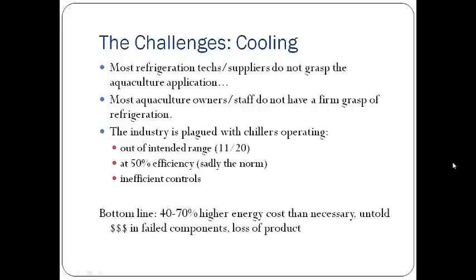In fact, they didn't even publish any data for the range that they were being operated in. So they were being run very inefficiently. But even some of the ones that were in the intended range were operating at roughly 50% efficiency. And the method used to control chillers and incorporate them into the aquaculture system is often done inefficiently, simply out of the knowledge gap that exists between aquaculture and refrigeration. The bottom line is 40 to 70% higher energy costs than necessary for cooling water.